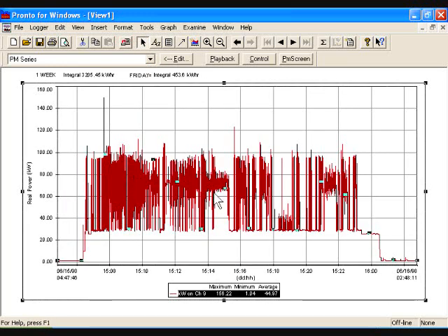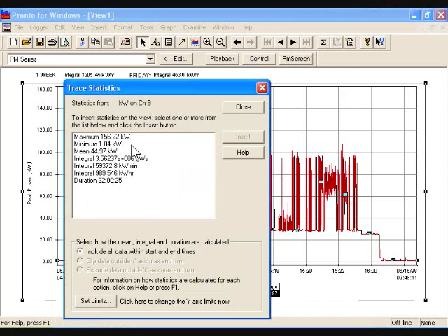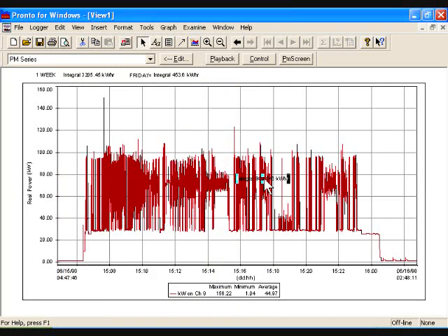We're going to zoom in just on the Monday. We're going to go grab our cursor, click on the line, put the little handles on the line. We have the Greek letter sigma here again. We click on that, and we'll notice that the kilowatt hour usage on Monday was 989.546 kilowatt hours. If you click on that and we insert that in, and so now we have the integration, the area below the curve for the total kilowatt hours used on Monday. And you'll notice that if we put this up here, remember Monday was a much more active day than Friday was, to the point where it was more than twice as much as Friday.